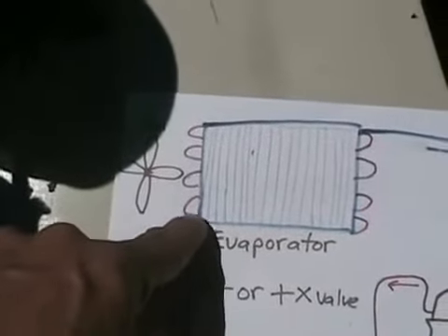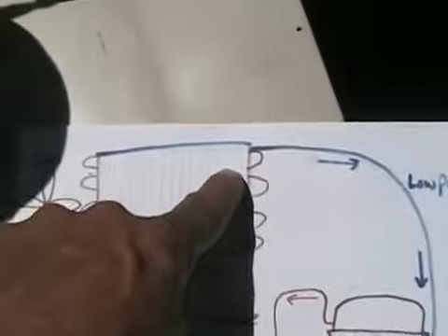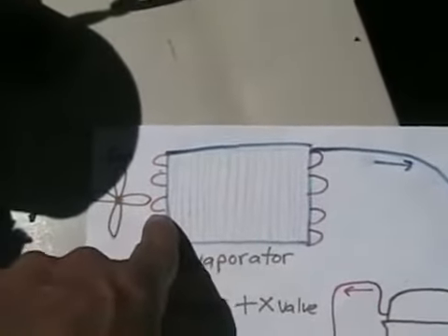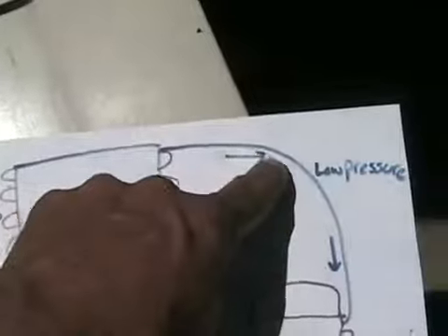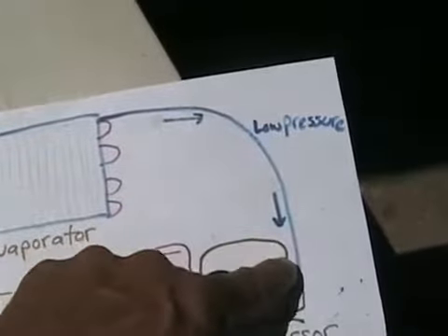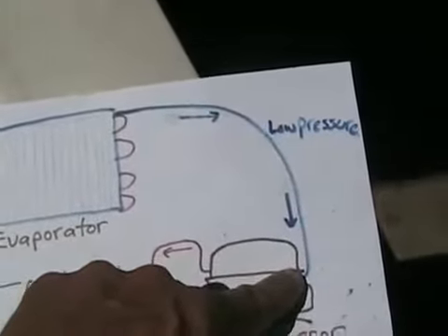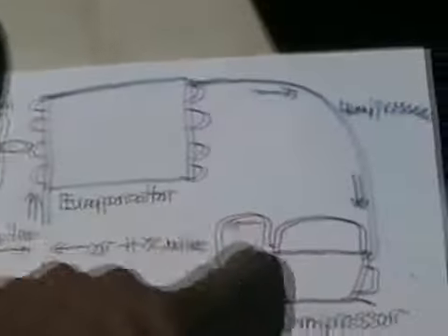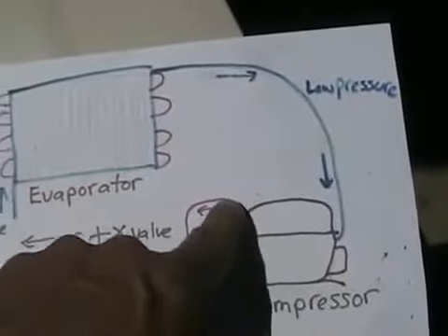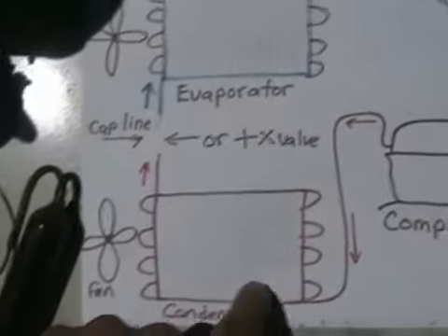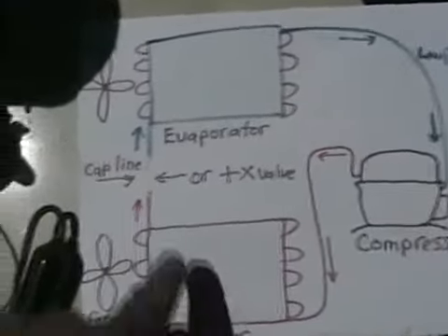So the liquid Freon is now foaming and bubbling as it's going through all these little tubes, and the fan is blowing on the radiator. By the time it gets to the top, or the end of the radiator, it's now a pure gas. Well, the pure gas is now warmed up to whatever temperature the room is where the fan is. And the pure gas goes back to here, now containing quite a bit more heat than it did before, especially than when it came out here, and gets recompressed again. And then the heat, of course, is exhausted by the condenser. So that's how all systems work.